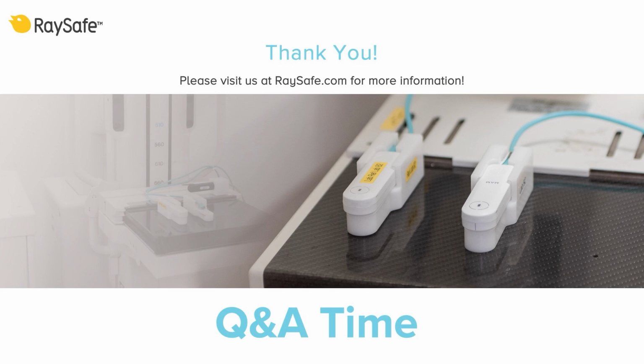Does the 452 perform dead time correction on the GM tube? Yes, it does. So there is no need to do any adjustments of your readings or anything like that. So you can just use it as a regular.